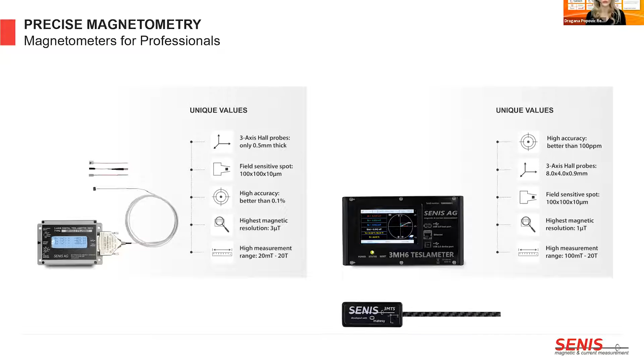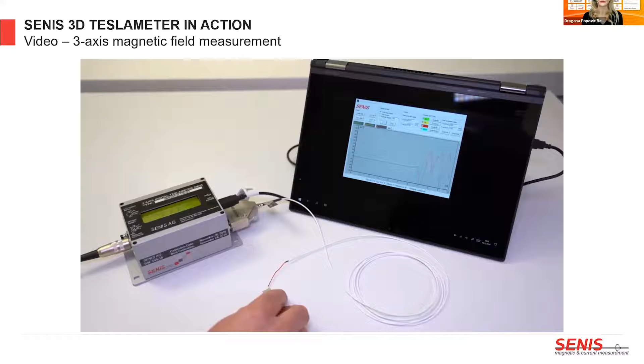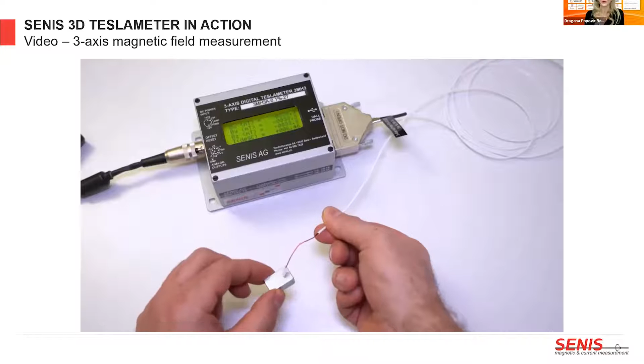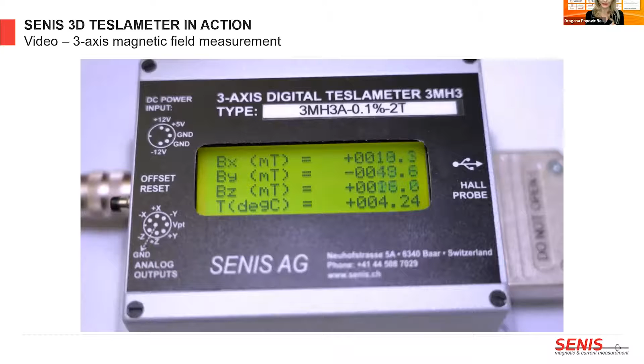Here the Tesla meter is connected to a computer with an acquisition and visualization software. The Tesla meter is based on a high accuracy magnetic field to analog voltage transducer. It provides a temperature compensated output signal for each of the 3 components of the measured magnetic field, Bx, By, and Bz. A digital module is applied to the analog transducer, allowing the measured values to be visualized on a display and also by a computer.